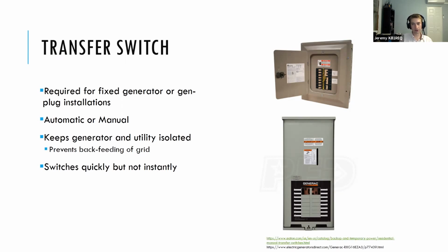It also doesn't hurt, if you're relying on a backup generator, to keep that UPS runtime longer than the typical switchover, just to prevent any issues with automatic startup, right? If the generator doesn't turn over in a couple of minutes, you've got to go start it manually. You want to build in some buffer on your UPS side.